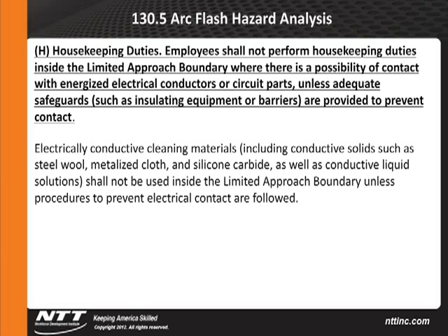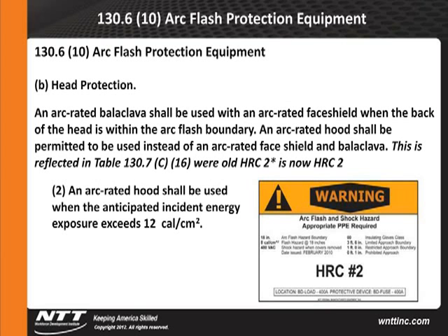Arc flash protection then. What about head protection? And again, remember I was telling you before in those earlier tables, the old category 2 with the asterisk is gone. Well, here's the requirement for head protection. An arc-rated balaclava shall be used with an arc-rated face shield when the back of the head is within the arc flash boundary. An arc-rated hood shall be permitted to be used instead of the arc-rated face shield and the balaclava. Again, a significant change in PPE that's going to go on an employee's head.